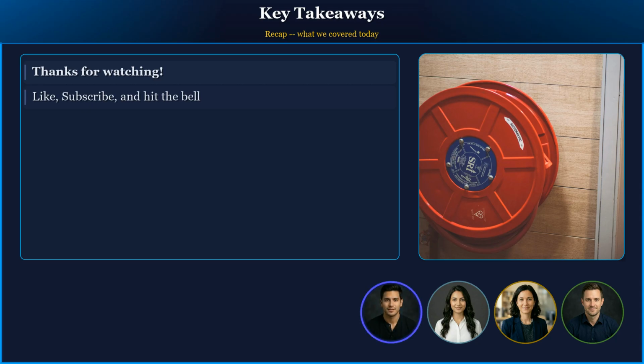The OVH Cloud fire showed that when physical controls fail, digital controls are irrelevant. Fire suppression must match equipment density. Backups must be off-site. UPS units themselves can be fire sources. Physical security is not a box to check, it is a discipline to maintain.